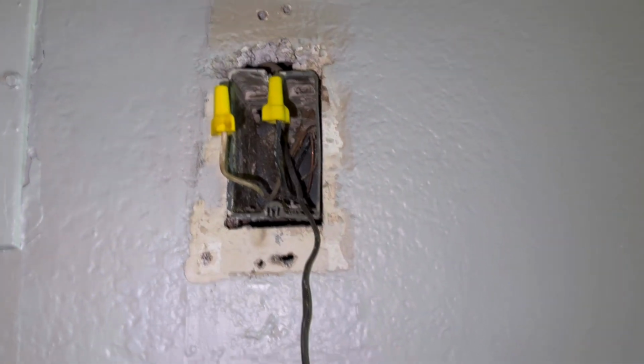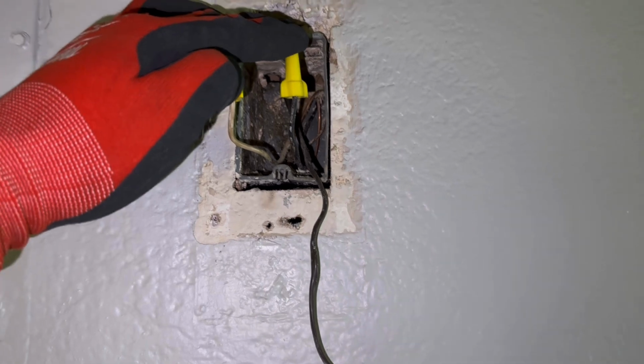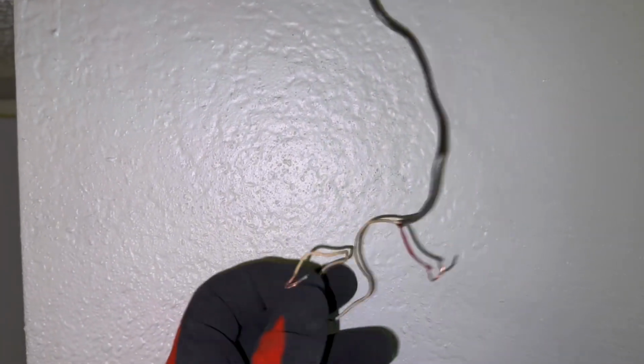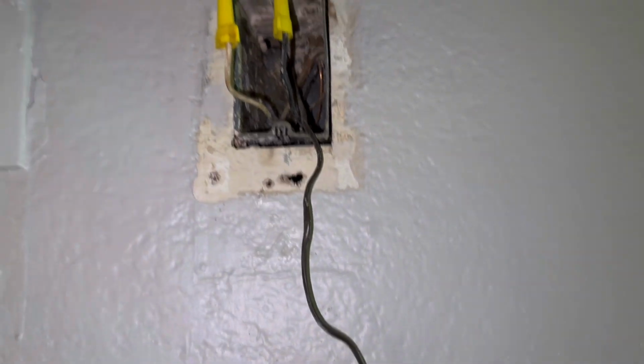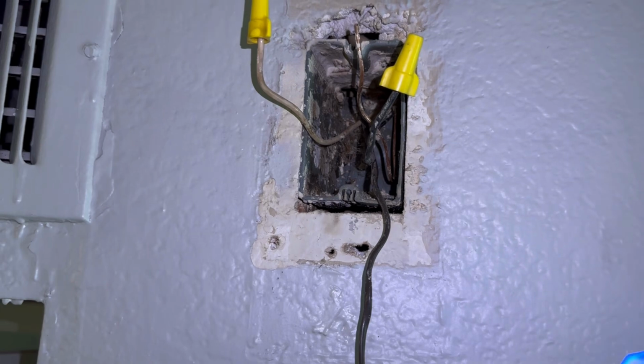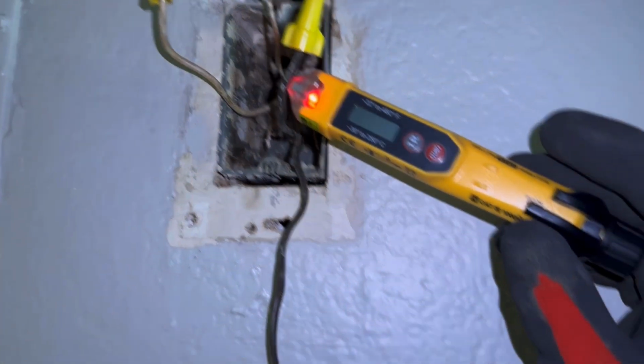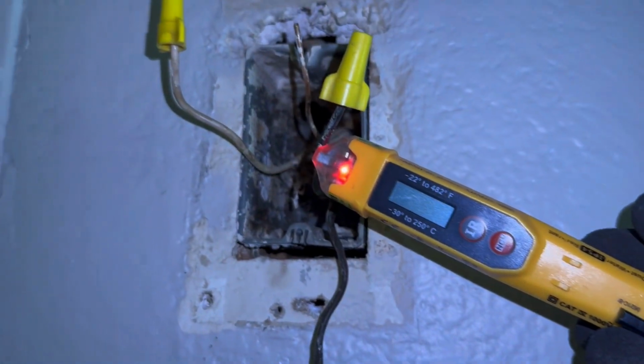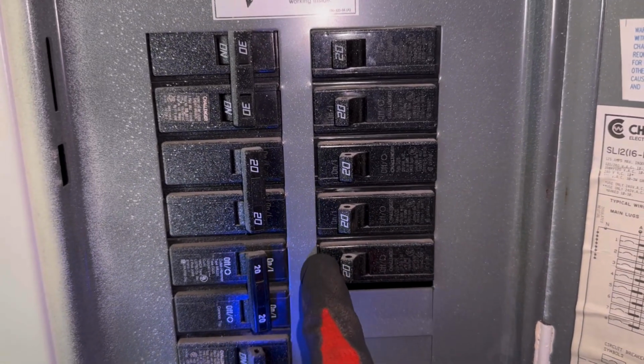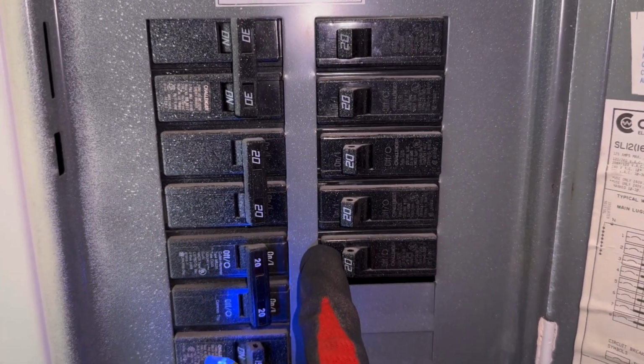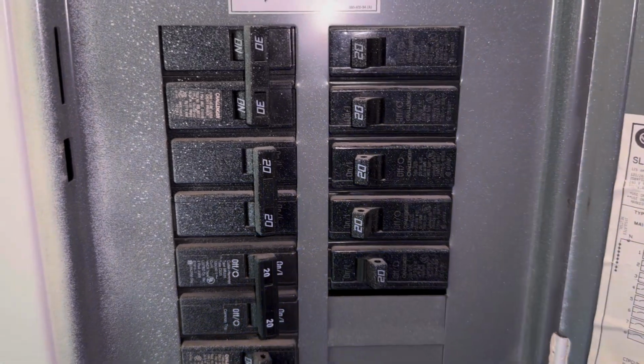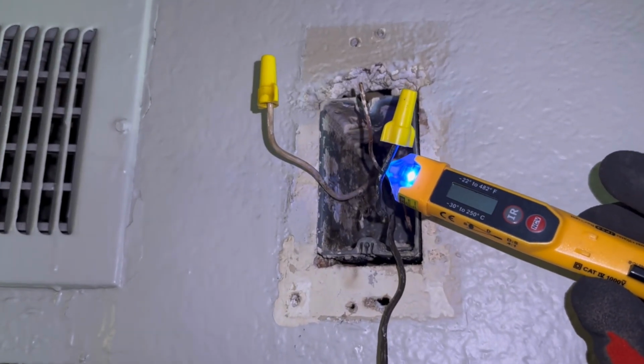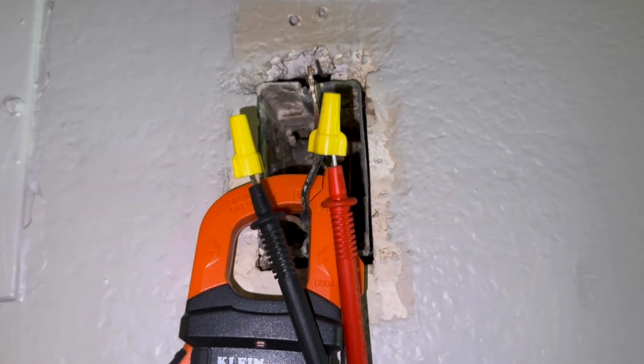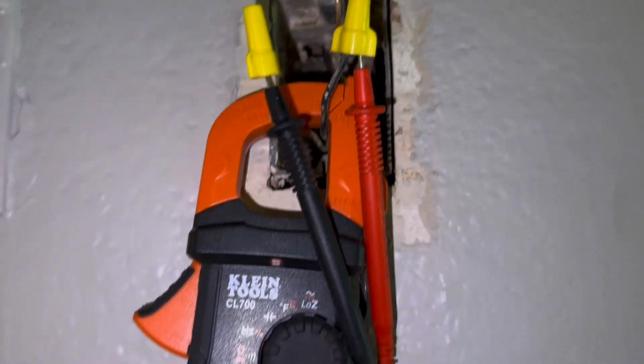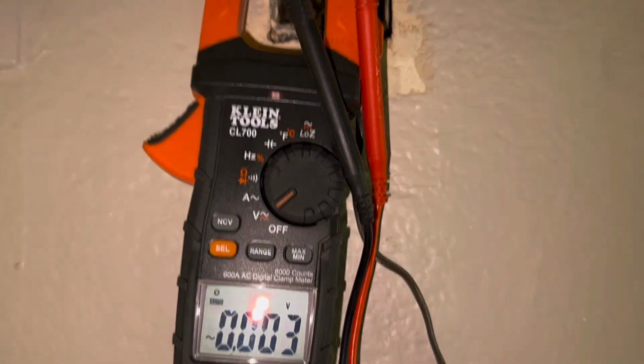Now that we know we have 120 volts feeding the lines, we've tested our continuity for our low voltage wires going to the doorbell button. Now we're able to start our install. You can also use your non-contact voltage detector. This is indicating to me that I do have power. We're going to turn the breaker off that feeds the power to the lines for the transformer. You can see here I am not getting any power to the line. It's always good to double check. So here I'm rechecking with my multimeter and I have no voltage.